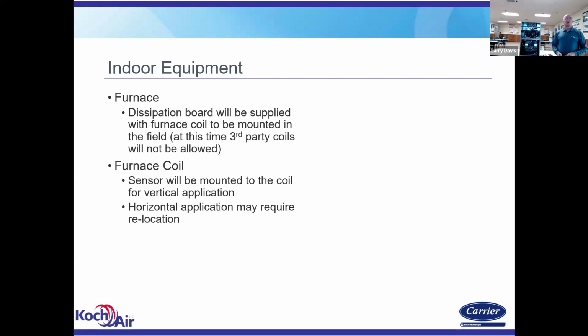So if you're using a furnace, the dissipation board doesn't come with a furnace. We don't know if that furnace is even going to have air conditioning on it, and it doesn't have any refrigerant in it. So there's no dissipation control coming with furnaces. Nothing's going to change there. It's going to come with the furnace coil.